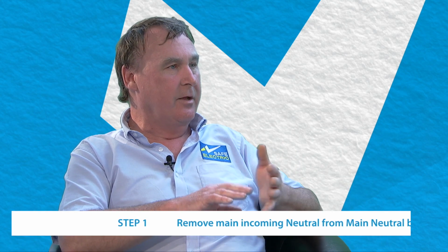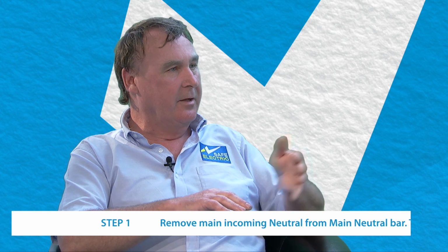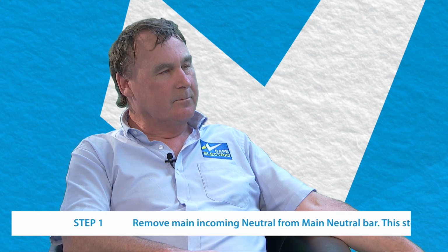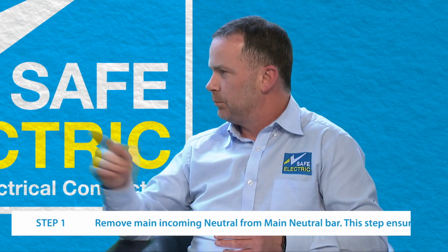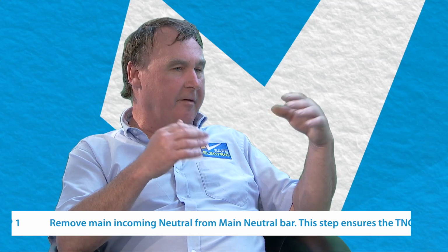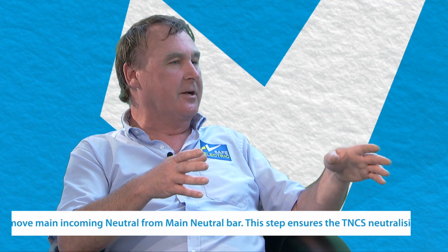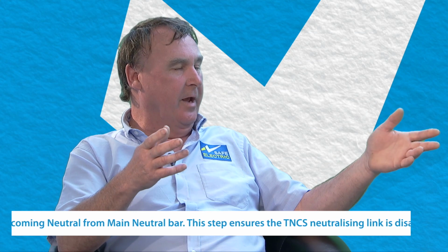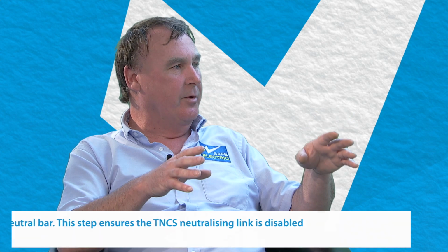Step number one is to remove your main incoming neutral, which is normally... That would only be an energized installation, though. For somebody doing it for the first time, you wouldn't need to do that. Exactly. I find if you stick to consistency, you'll always get it right. Of course. So step number one is get your blue 16-square incoming neutral and remove it from the neutral bar.